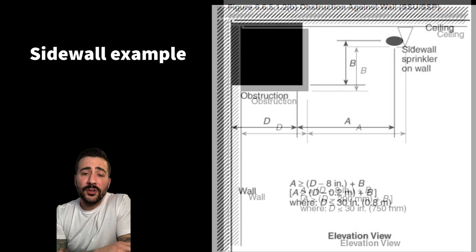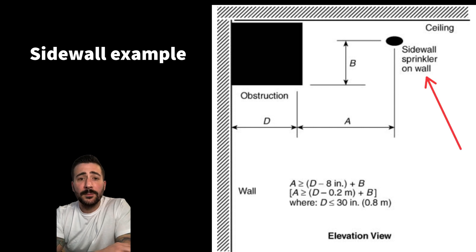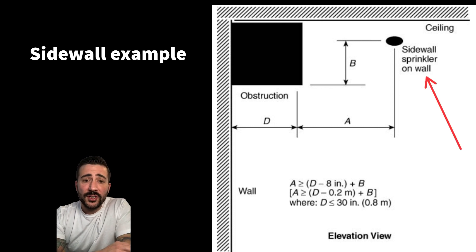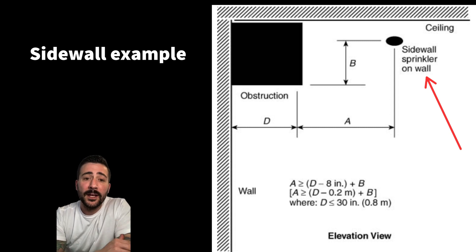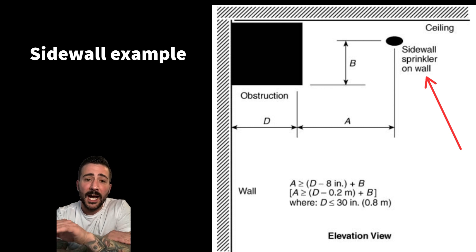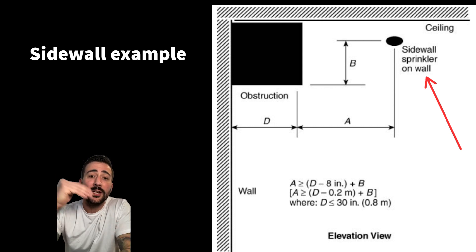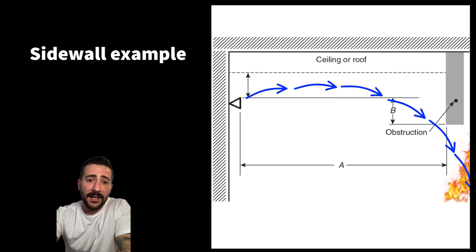If we are going to use the Soffit Rule for one of the available sidewalls, it is for obstructions against a wall located on the same wall as the sprinkler. This is not to spray under obstructions across from the sidewall. If you're trying to spray under an obstruction located on the opposite side of the sidewall, we're going to use the Beam Rule for that specific head.